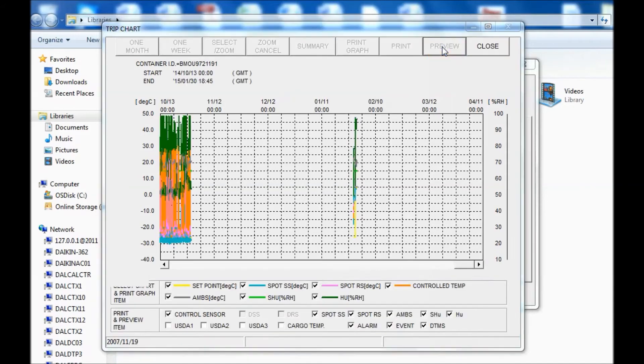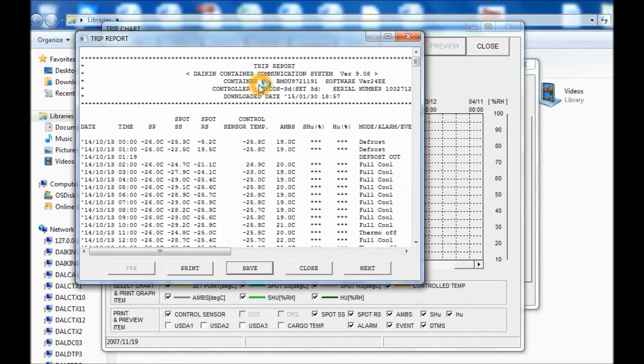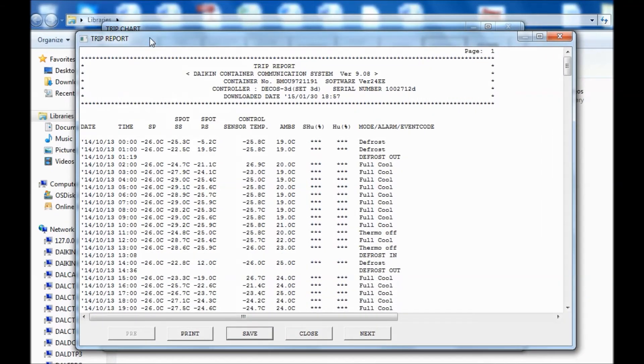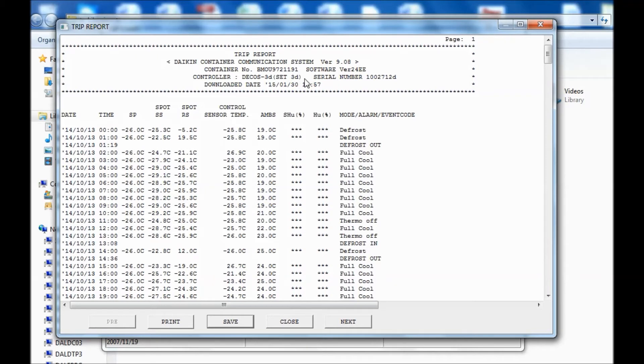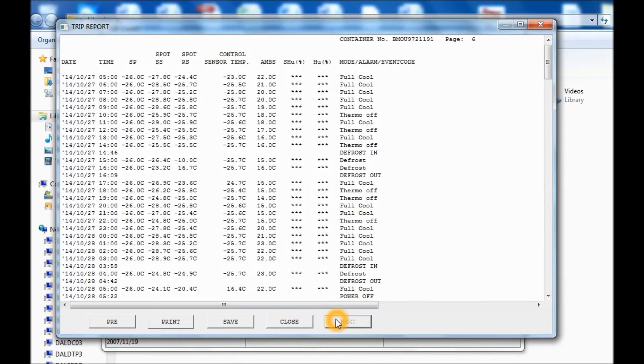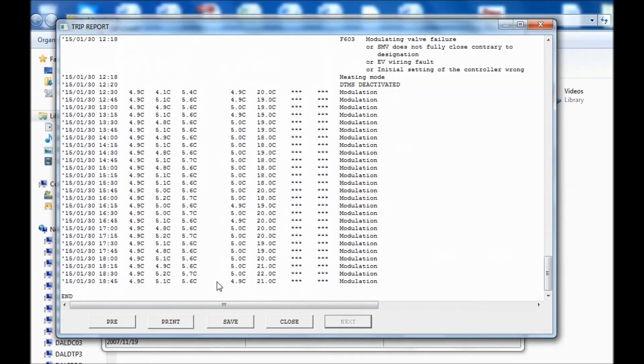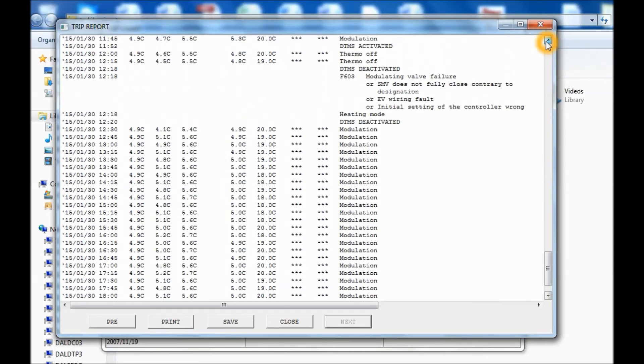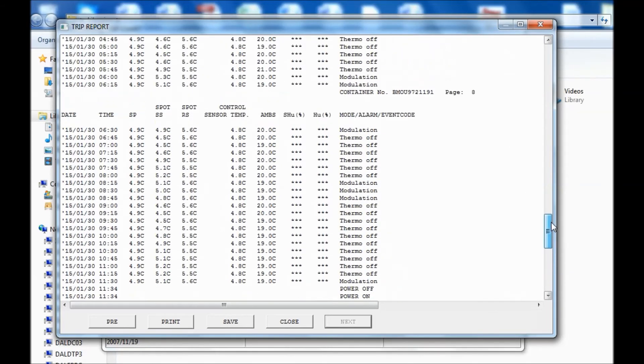So if you want to see a text view, you can go here. Let's widen this up a little bit. And so you have your header up top. Daikin Container Communication System, container number, software version, what controller it is, and the serial number and download date. And if we scroll all the way back... So we did a download today. Actually the date is incorrect on this controller. But here you can see kind of the example. F603 alarm on this one.